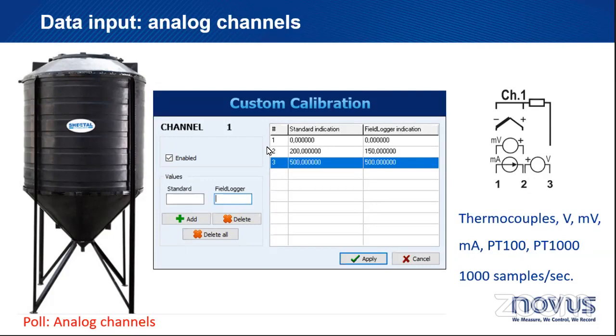The other example would be, I'm measuring a sensor and I would like to have a calibration point. I would like to have an adjustment point at 200 degrees. My sensor is reading 200 degrees, but it's actually 203 degrees. I want to add that calibration point. You can do that, okay? So all of them, you can use that configuration, and these will really allow you to do several different things.